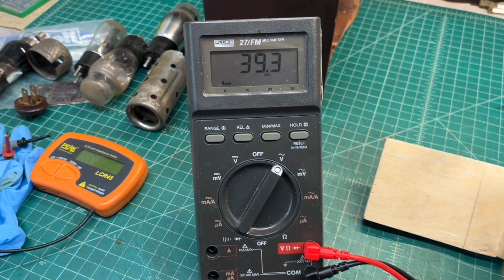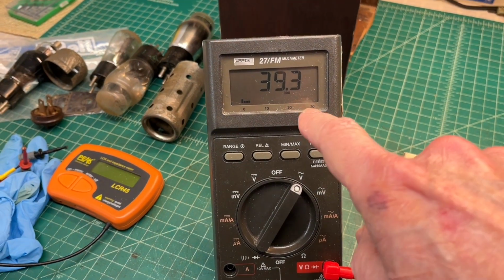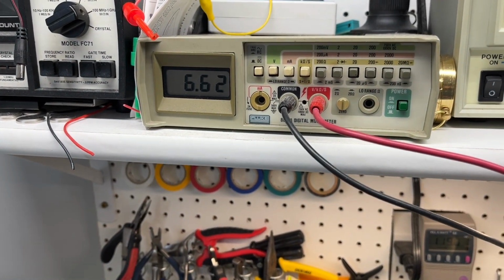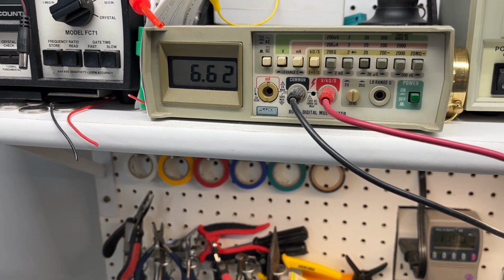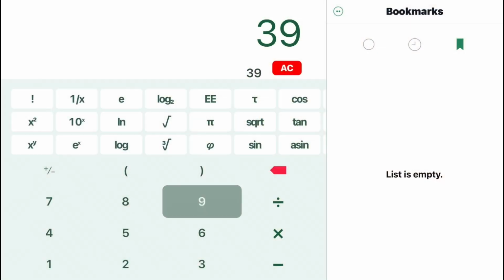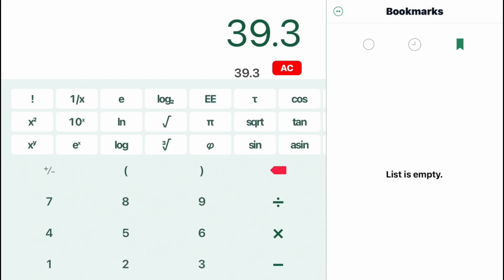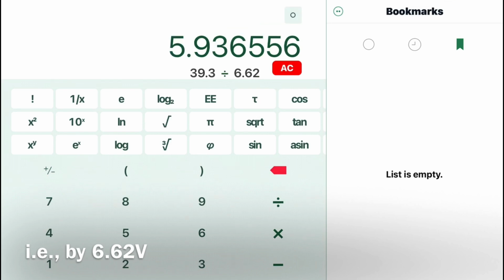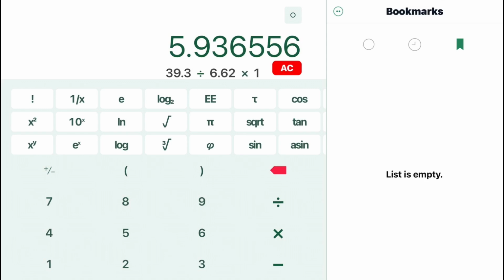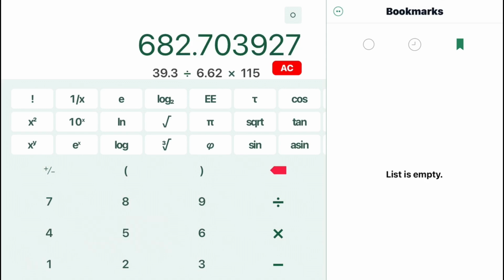Lastly, I'm checking across the two plates - we'll look at the whole high voltage winding. You can see the readings on the meter; let's plug those into the calculator. We'll take the 39.3, divide that by the 6.62 volt input voltage, and that gives us a ratio of 5.9 and some change. Multiply that by the 115 volt AC line input, gives us 682.7, so right at 683 volts.